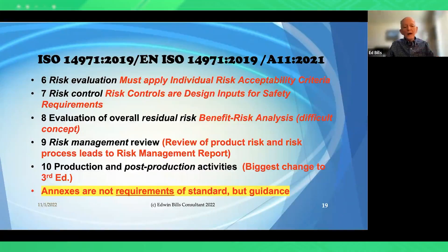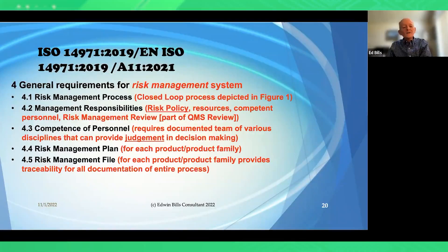When you collect information, review it to find out what's going on with your product's risk performance, then take action: how urgent is the action needed? Is this an immediate recall? Look at both the product itself and your risk management process — there may be a defect in your risk management process that needs to be corrected. Clause four covers the risk management process as a closed loop. The competency section requires a documented team of various disciplines capable of providing judgment and decision-making. A risk management plan is needed for each product or product family, including individual and overall risk acceptability criteria.